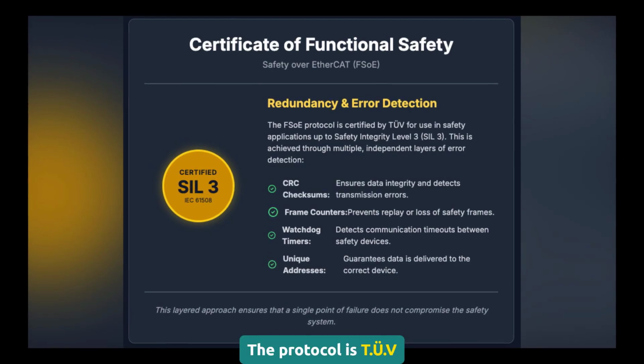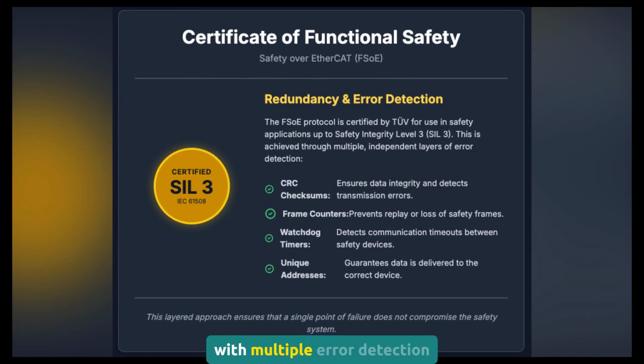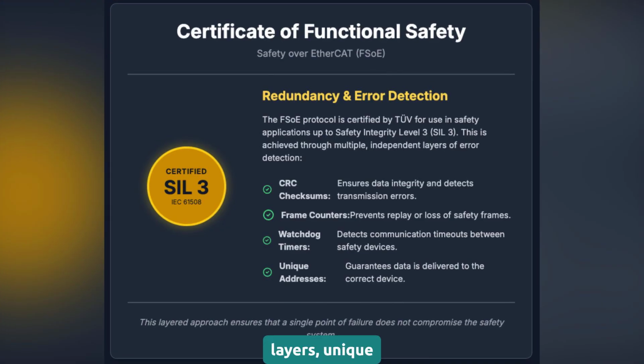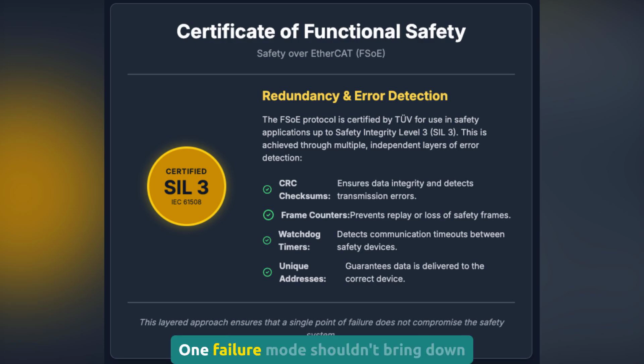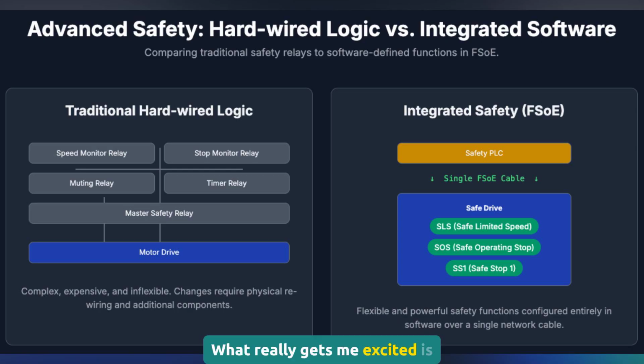The protocol is TÜV certified for SIL3 with multiple error detection layers: unique addresses, frame counters, watchdog timers, and CRC checksums. From an engineering standpoint, this redundancy makes sense. One failure mode shouldn't bring down your safety system. What really gets me excited is that you can implement advanced safety functions in software like Safe Limited Speed or Safe Operating Stop. Try doing that efficiently with traditional relay logic, and you'll end up with a cabinet full of safety relays and a wiring nightmare.